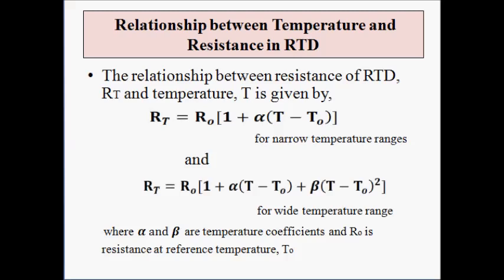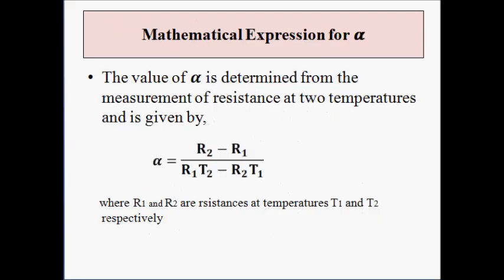The temperature coefficient of resistance α is determined by measuring the resistance of the RTD at two temperatures T1 and T2, where T2 is higher than T1. It is given by: α = (R2 − R1) / (R1·T2 − R2·T1). Here, R1 is the resistance of the RTD at temperature T1, and R2 is the resistance at temperature T2. By this formula, the positive temperature coefficient alpha is calculated.